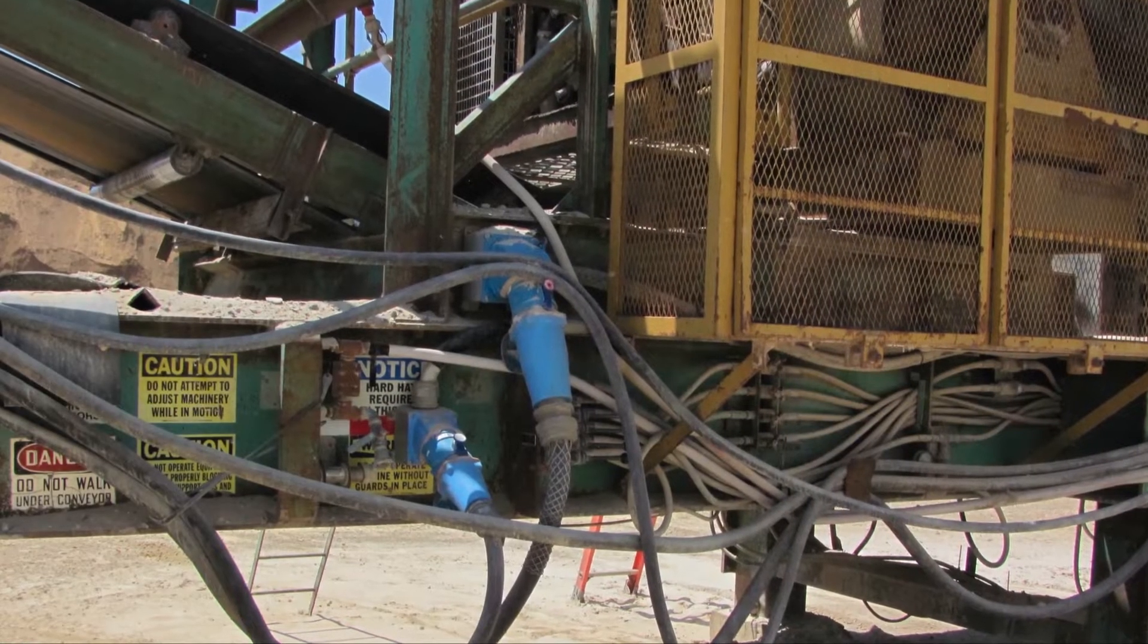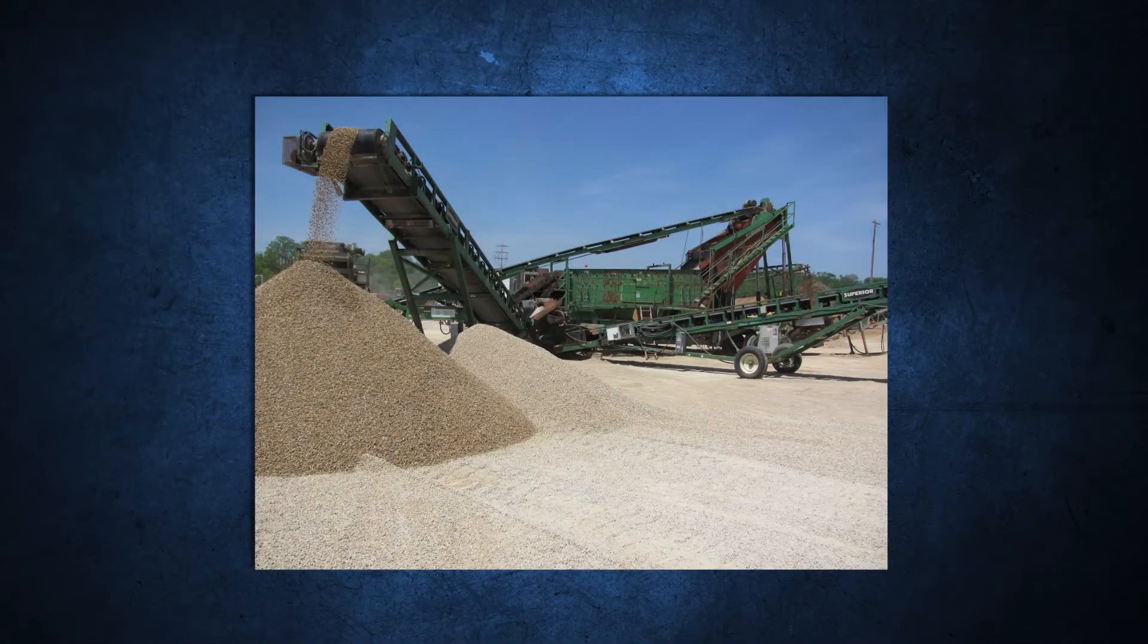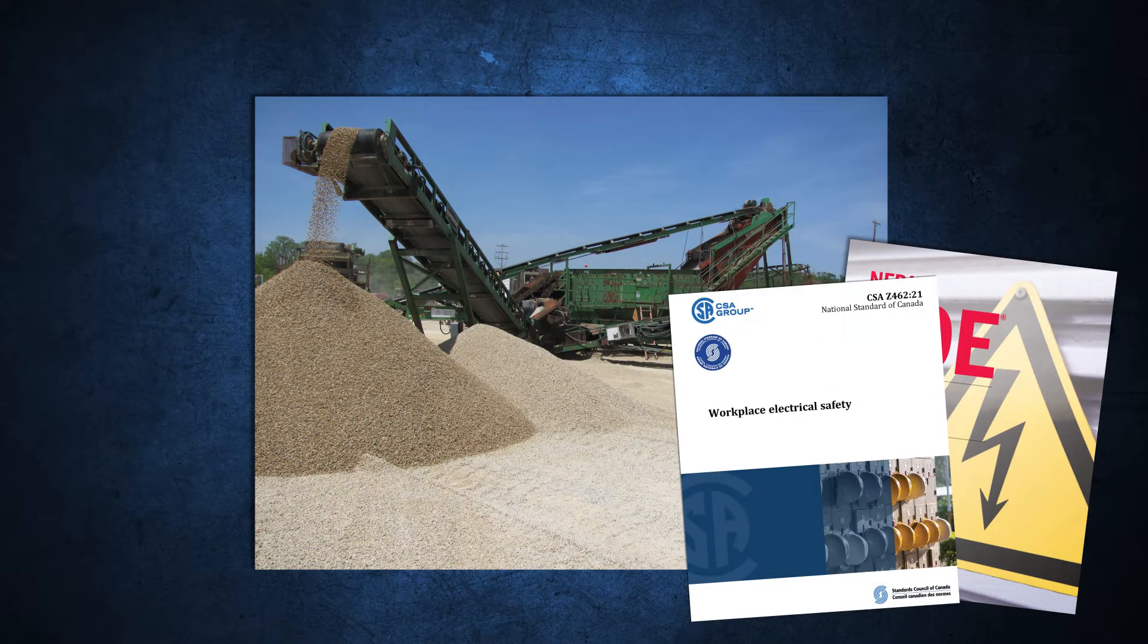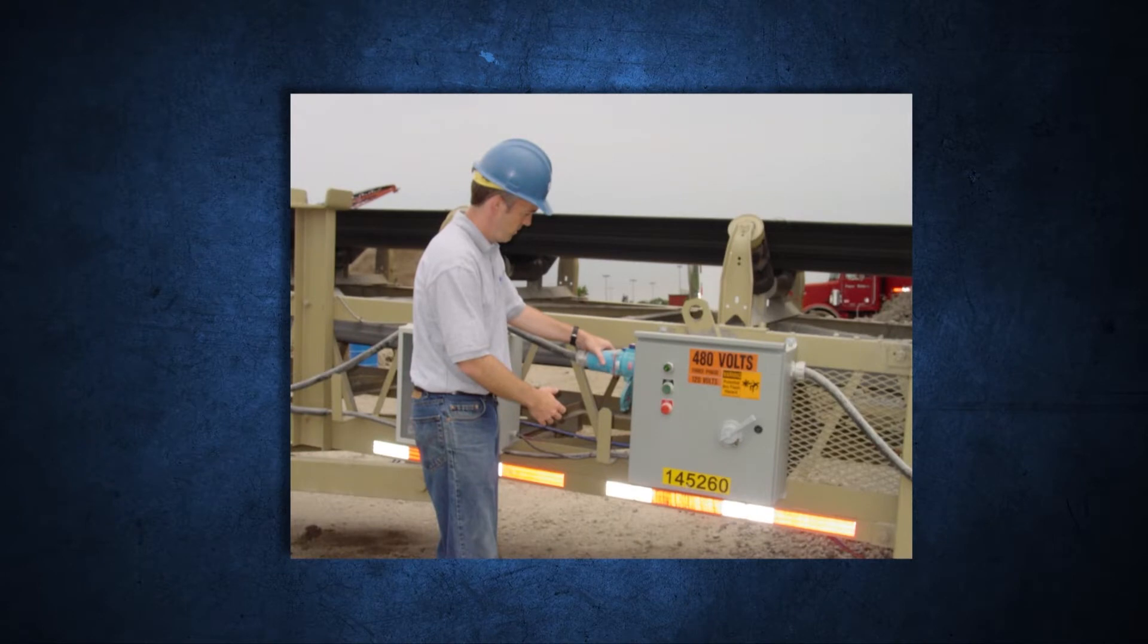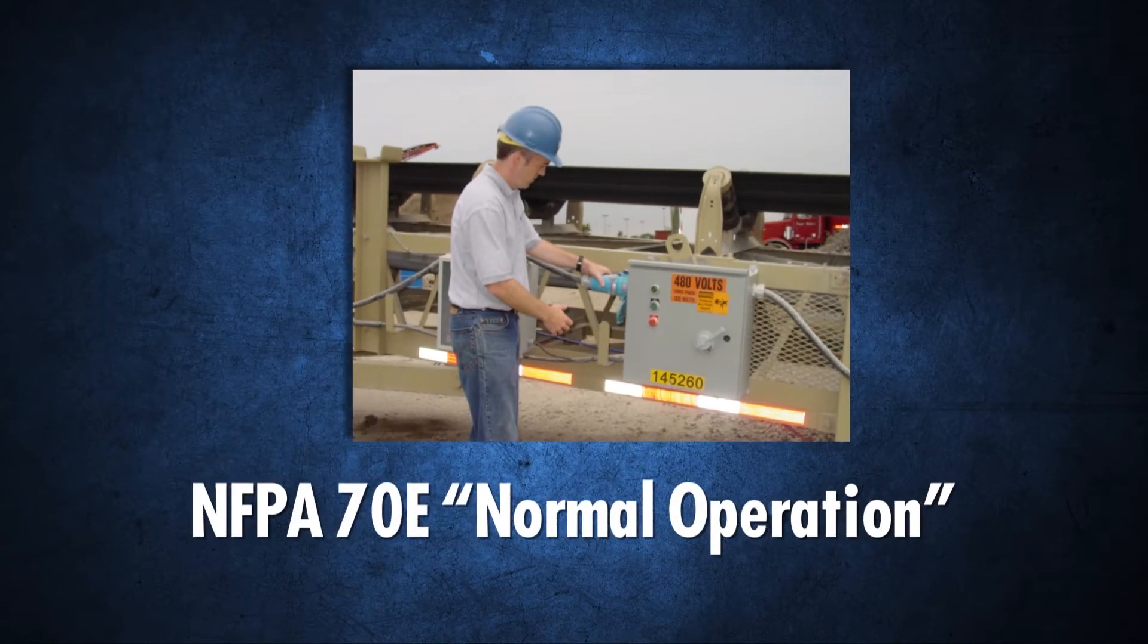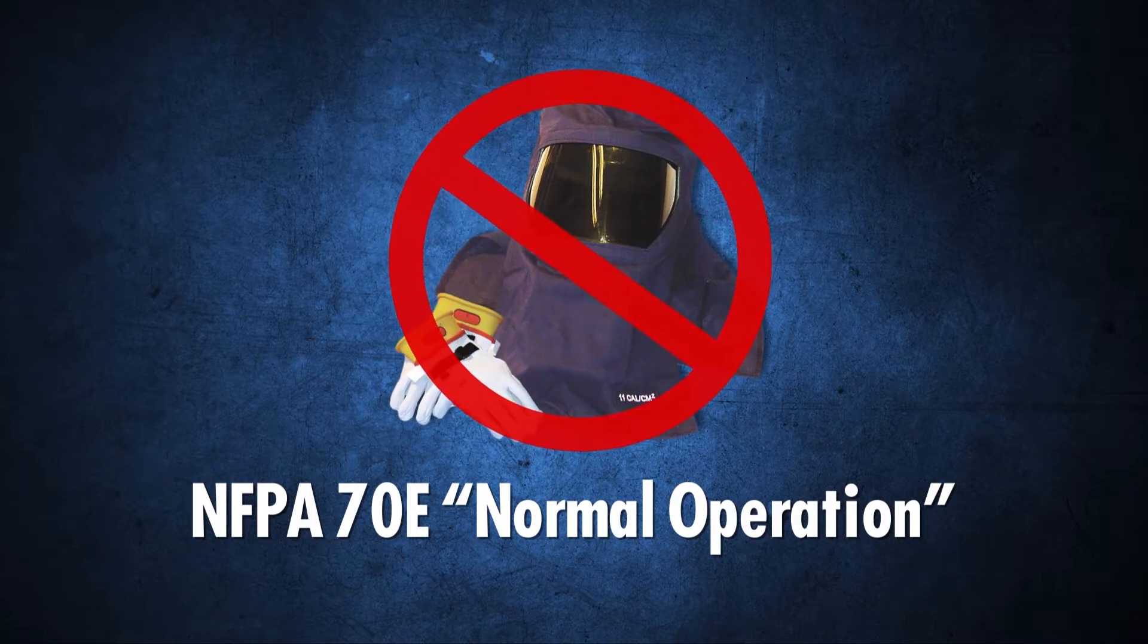Meltric switch-rated plugs and receptacles protect against arc flash and help facilities comply with NFPA 70E or CSA Z462 electrical safety standards. Connection or disconnection of the plug is considered an NFPA 70E defined normal operation, so PPE is not required.